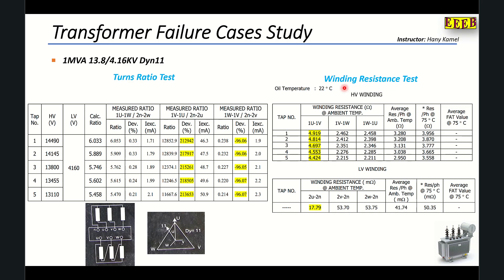To confirm this, we performed a winding resistance test. On the HV side, we have 1U1V, 1V1W, and 1W1U. We can notice that the summation of these two phases is equal to the third phase, and this actually indicates there is a cut in winding 1U1V. When we connect our leads for the winding resistance measurement, if there is a cut, the result will be the summation of those two windings. Our measurement confirms this cut exists, and we can notice this happens across all five tap positions.